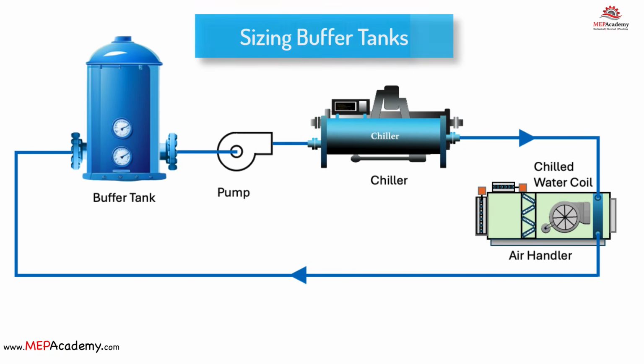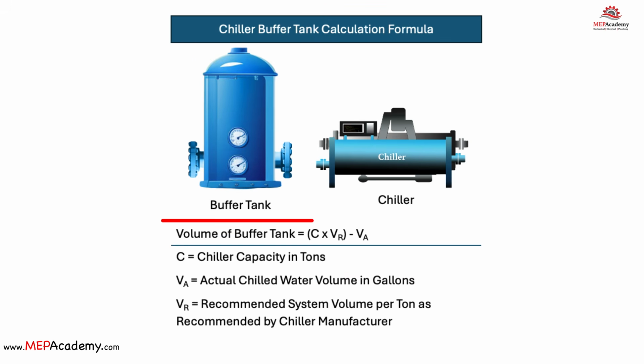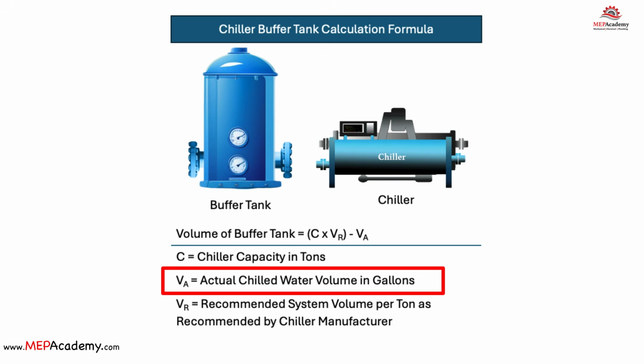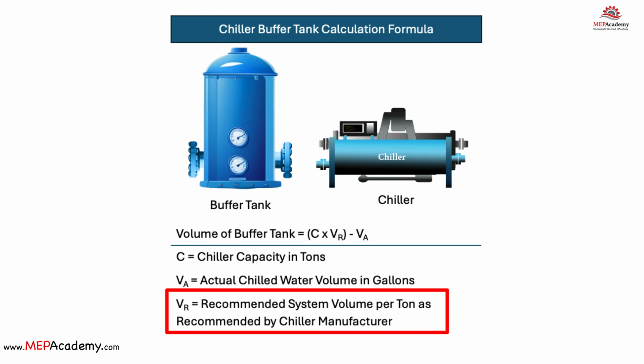Sizing buffer tanks. Here are two different formulas, one for a geothermal heat pump system and another for a chilled water system. Chilled water buffer tank sizing. The following formula is offered by one manufacturer of buffer tanks, and any calculations you make should be confirmed by a mechanical engineer or the manufacturer. Volume of buffer tank equals C times VR minus VA, where C equals chiller capacity in tons, VA equals actual chilled water volume in gallons, VR equals recommended system volume per ton as recommended by chiller manufacturer.